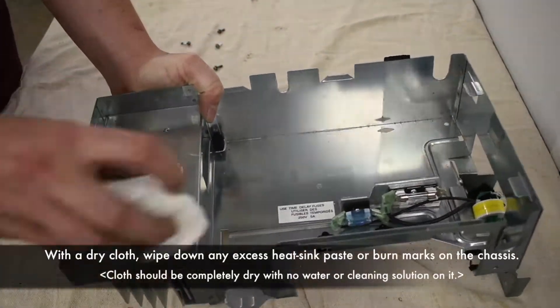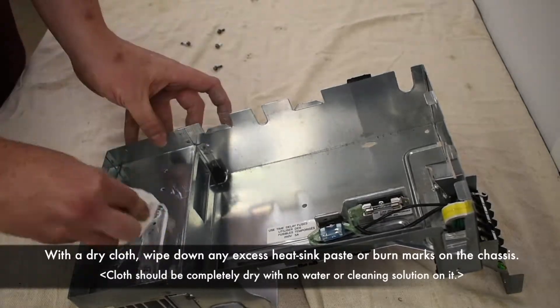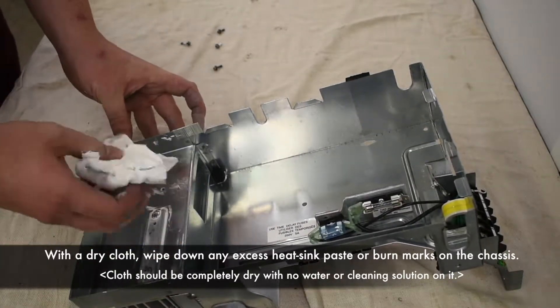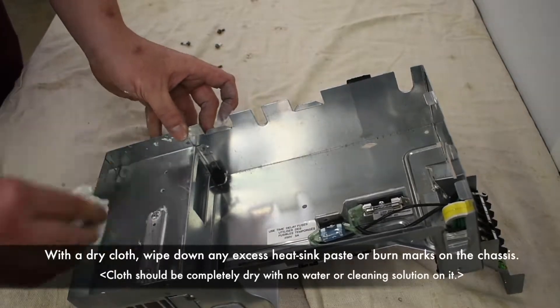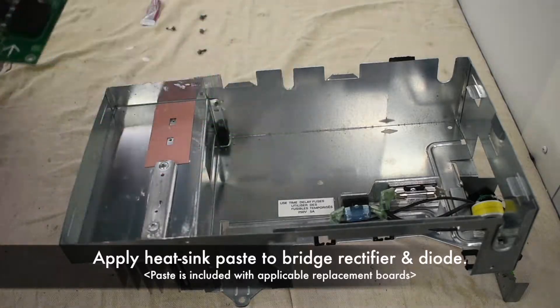With a dry cloth, wipe down any excess heat sink paste or burn marks on the chassis. Apply heat sink paste to the bridge rectifier and diode.